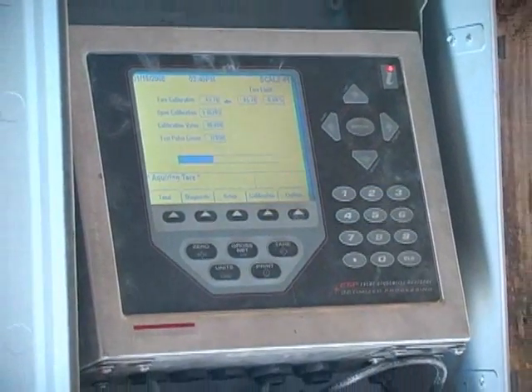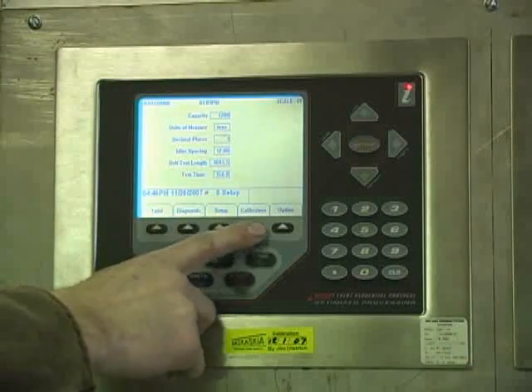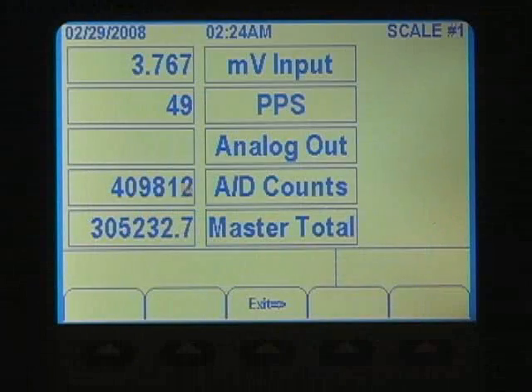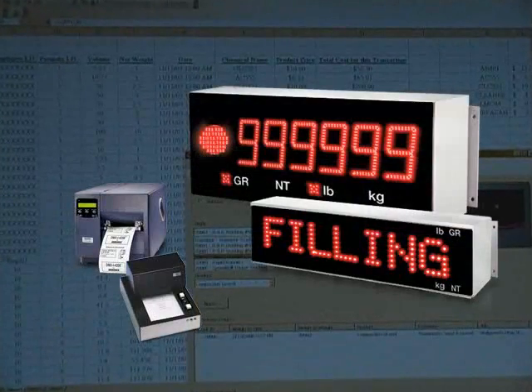Optional multiple analog outputs in either 0 to 10 volts DC or 4 to 20 milliamps, and a series of digital I/O points for signaling outboard gear are also available. Standard features include rate, speed, load, totalized weight, diagnostics, four bi-directional serial ports, ticket printing support, and four digital outputs. Optional features include a material accumulation system for PC-based tracking of commodities, and wireless interface to printers, remote displays, and other peripheral devices.